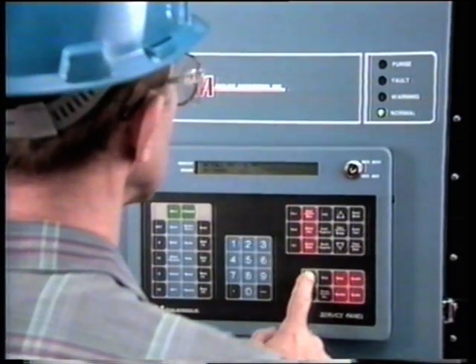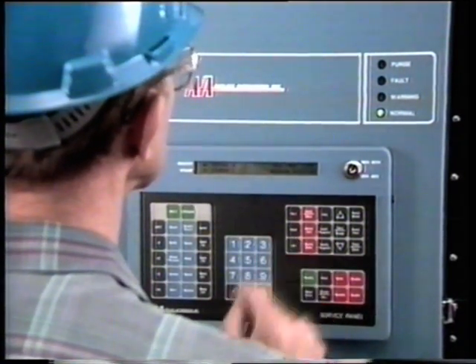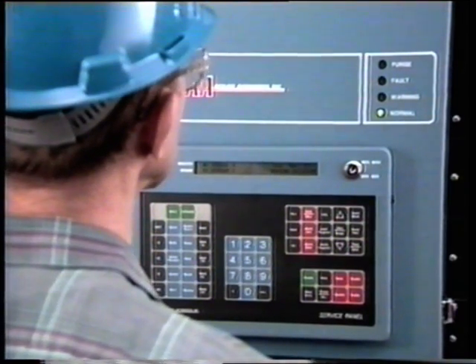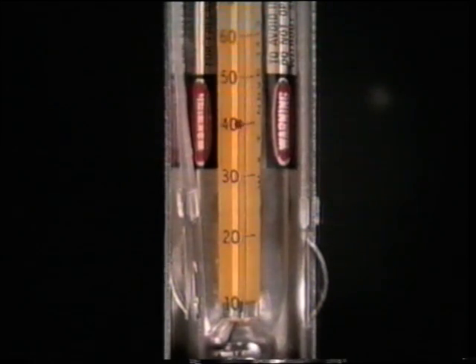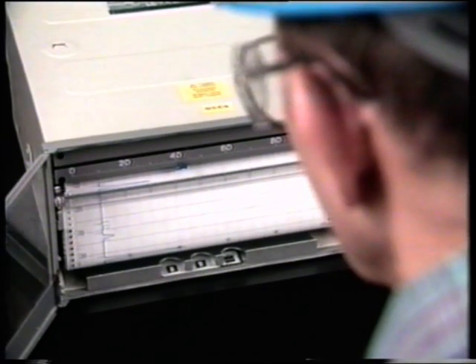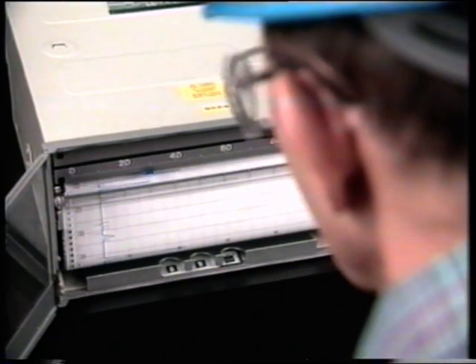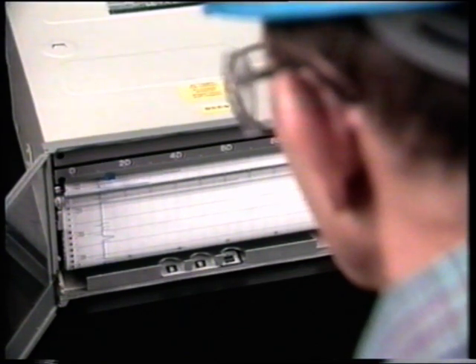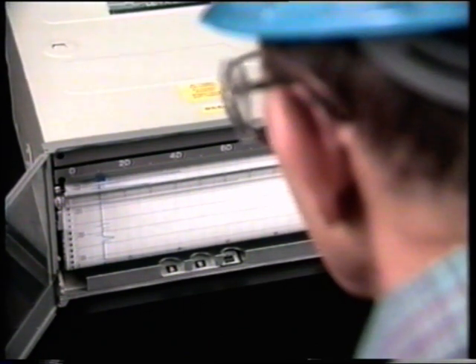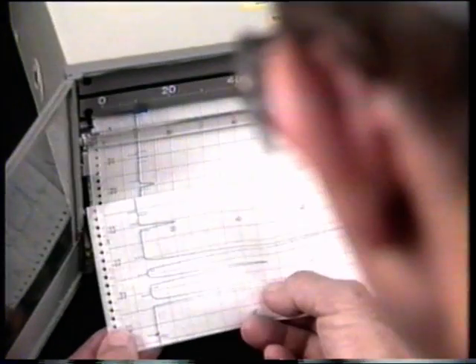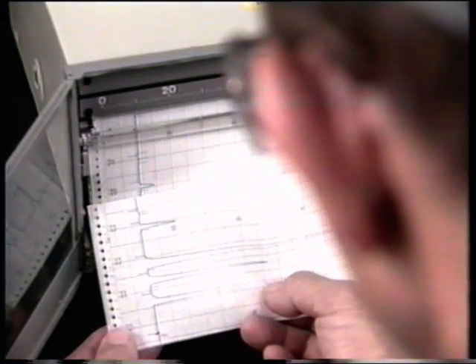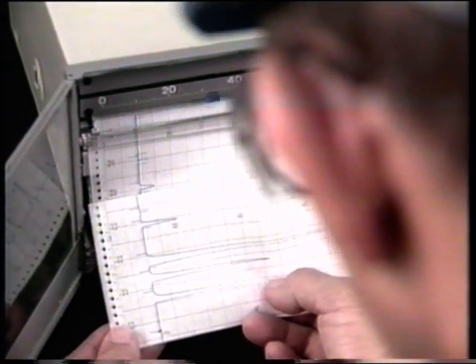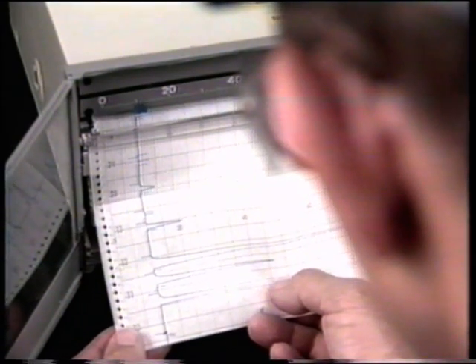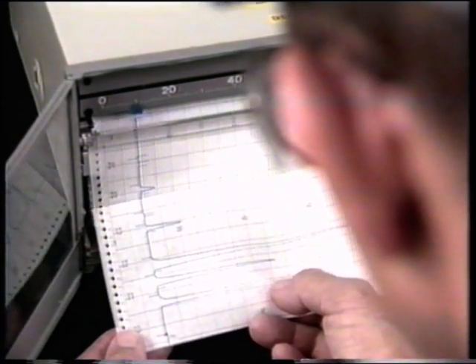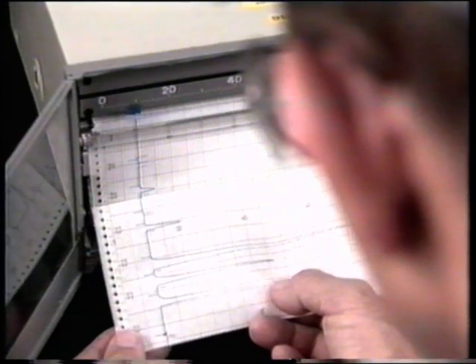When you have finished entering the calibration standards, start the calibration by pressing Calibrate. Check and adjust the sample flow rotometer. Allow the calibration to continue until the analyzer is sufficiently stable for at least 3 cycles to repeat within the specified tolerance. While the calibration runs are being made, examine recorded chromatograms to see that all peaks are within the gate and are of expected size.